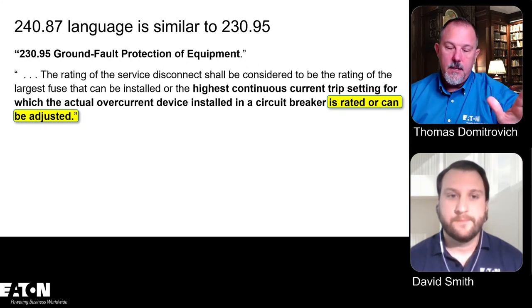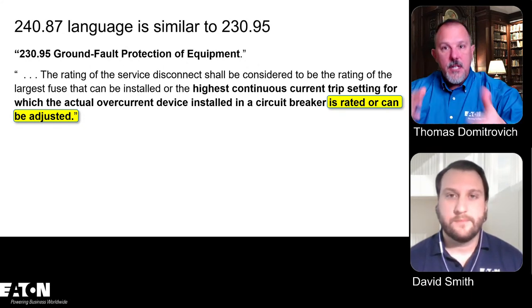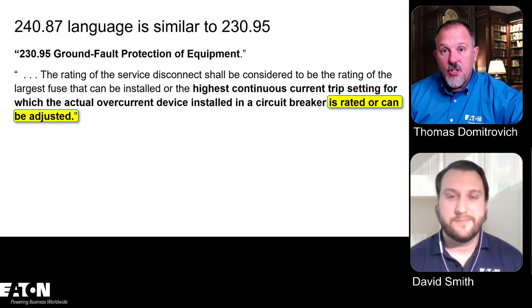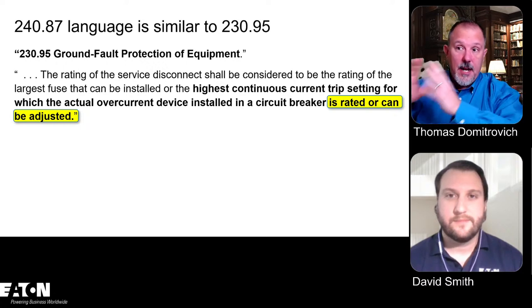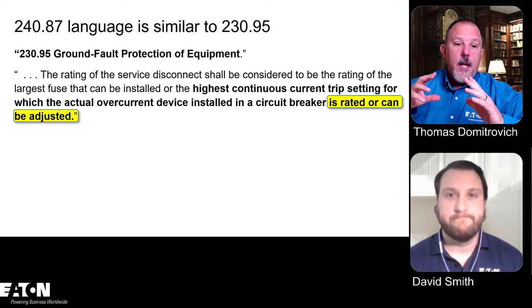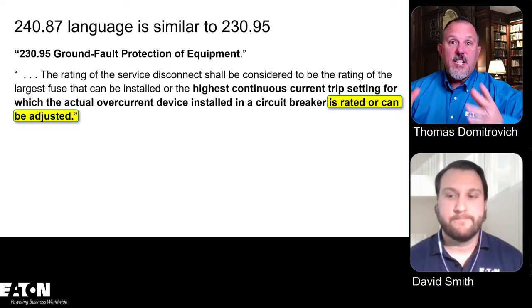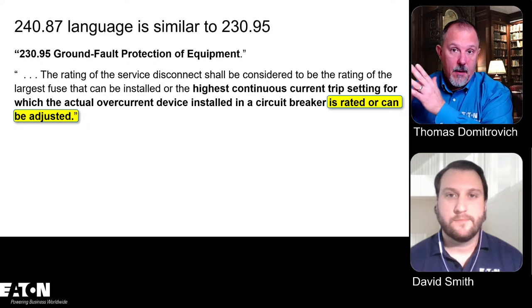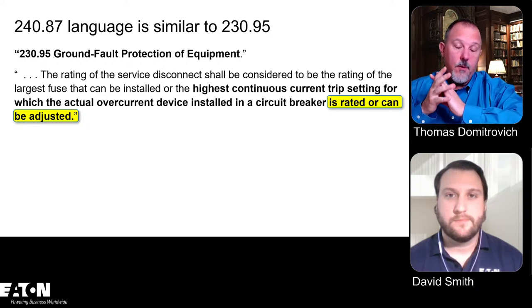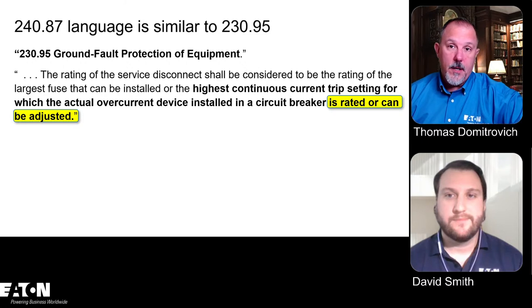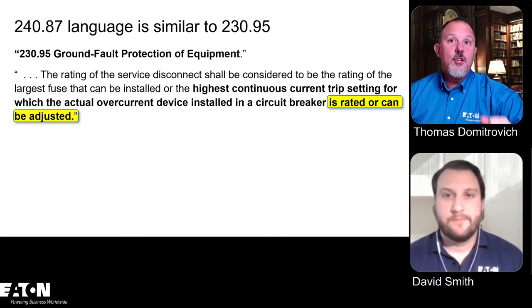regardless of its size. So I made a presentation to Code Panel 10 in the second draft meeting, and some of the slides from that presentation we have in our slide deck. Mm-hmm. And what I did was I explained to them the problematic issue with their language, which says basically they would have impacted every molded case circuit breaker and insulated case circuit breaker and power circuit breaker known to man that would be installed. Right. And that's very encompassing. And you saw the light bulbs go off.